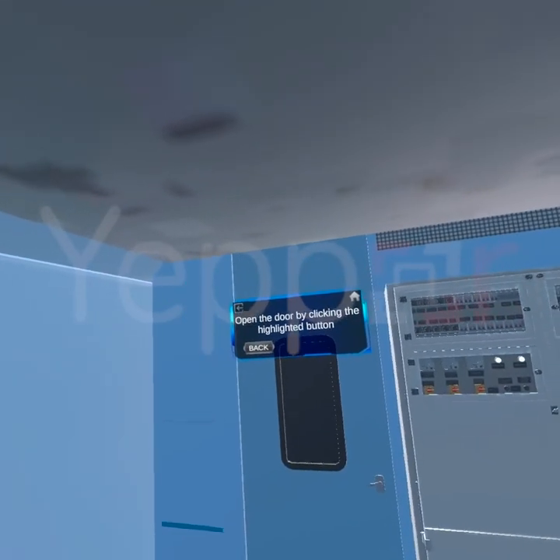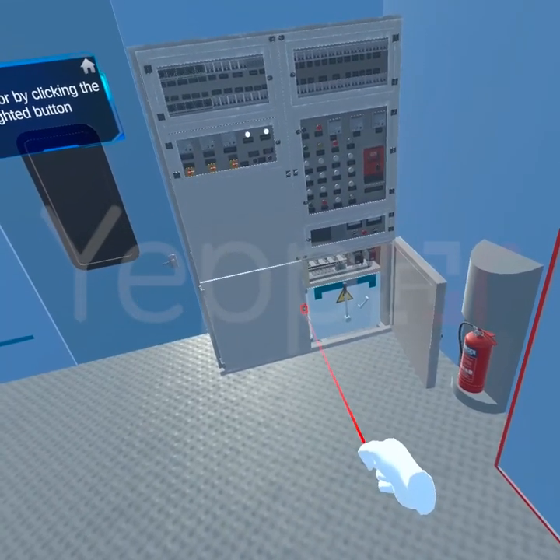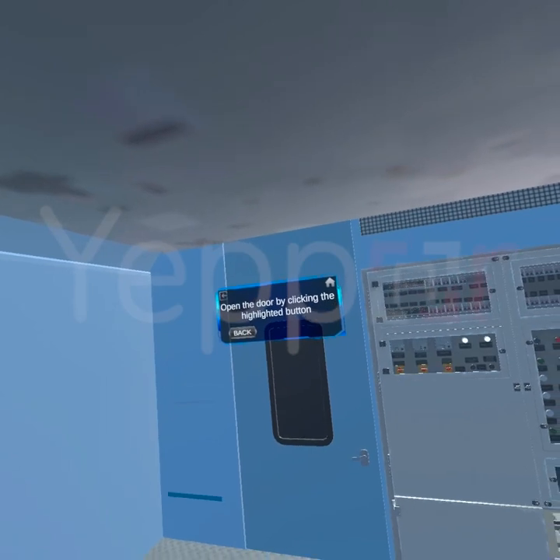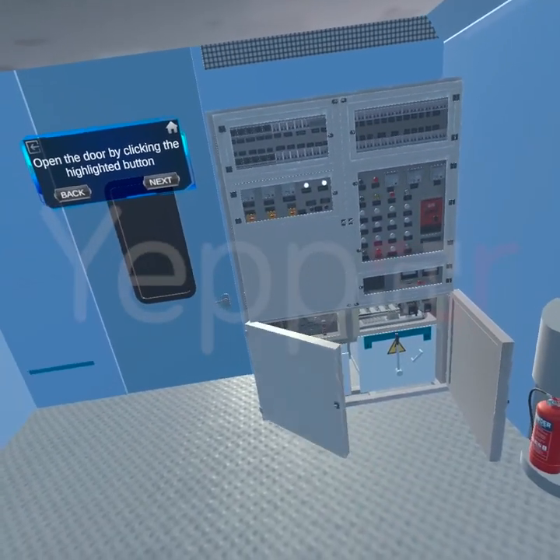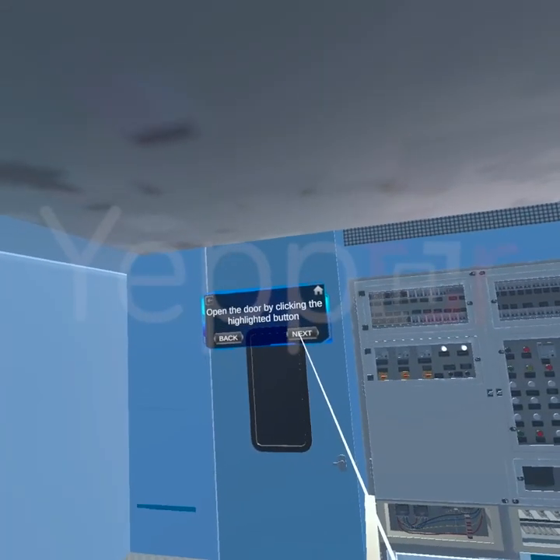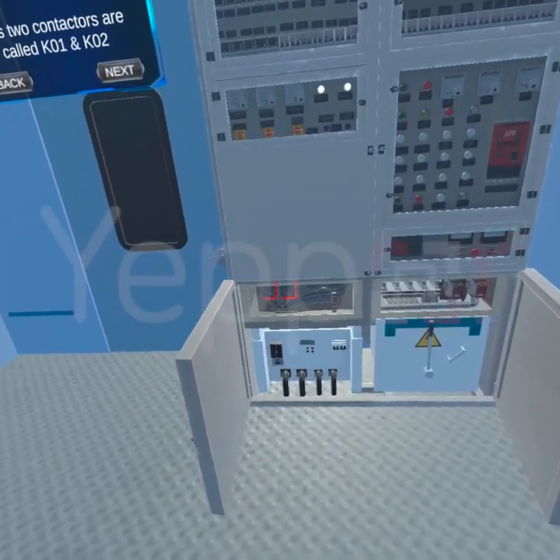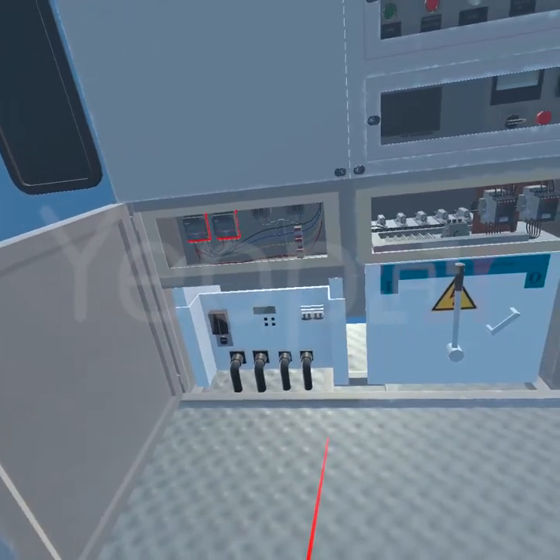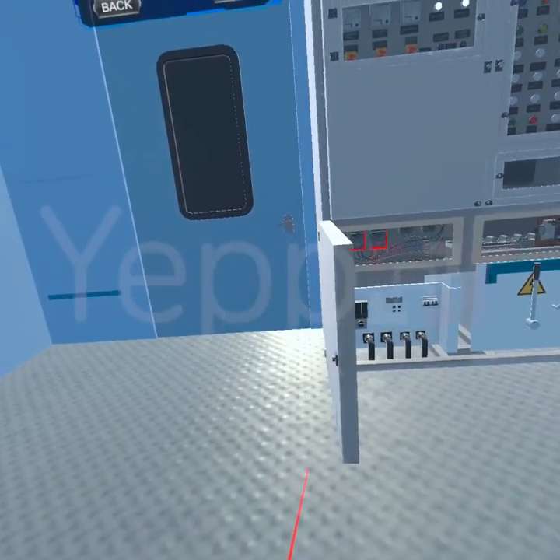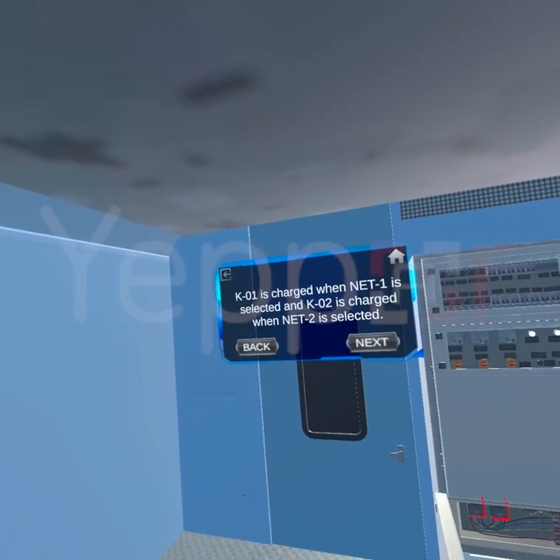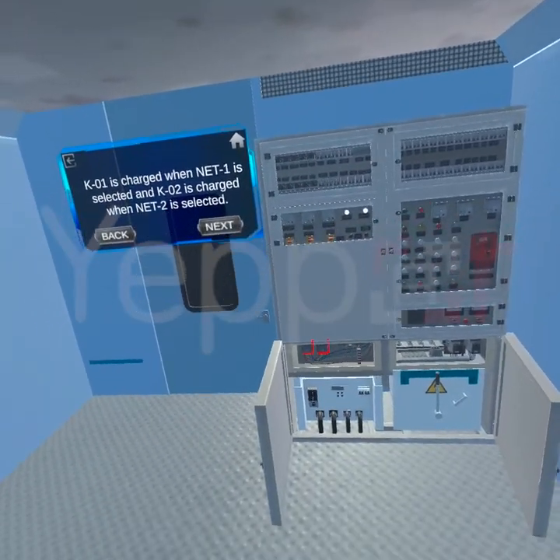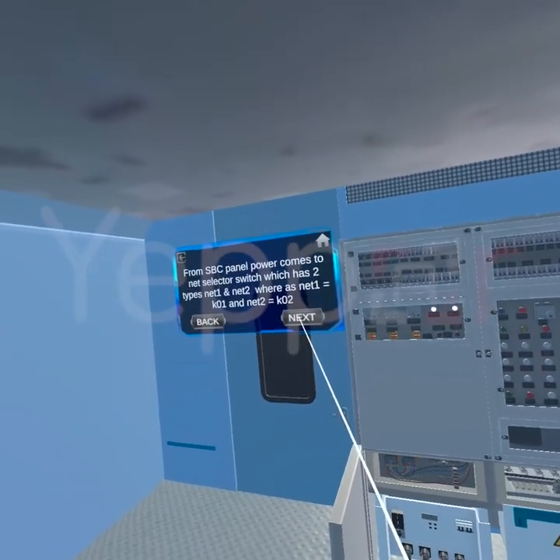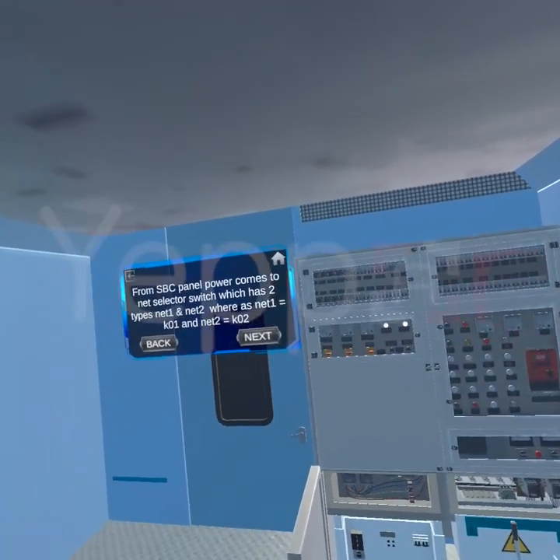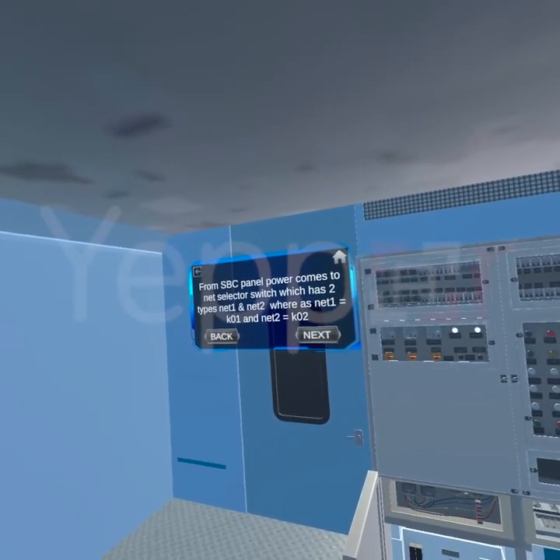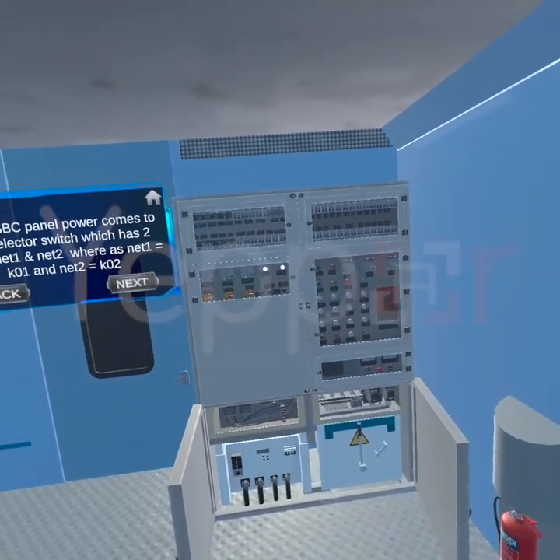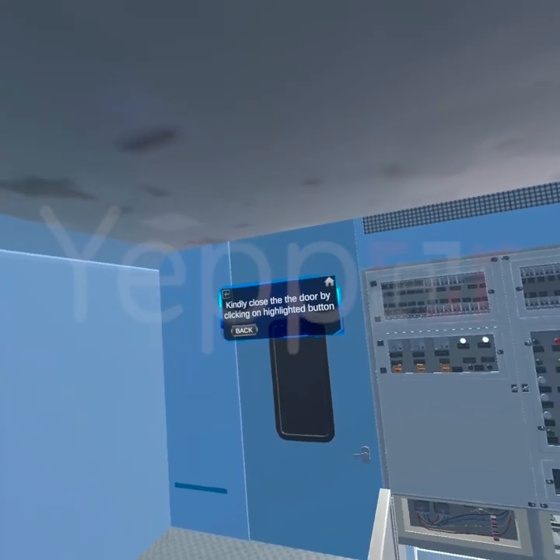Open the door by clicking the highlighted button. These two contactors are called K01, K02. K01 is charged when net 1 is selected and K02 is charged when net 2 is selected. From SBC panel, power comes to net selector switch, which has two types, net 1 and net 2, whereas net 1 equals K01 and net 2 equals K02. Kindly close the door by clicking on highlighted button.